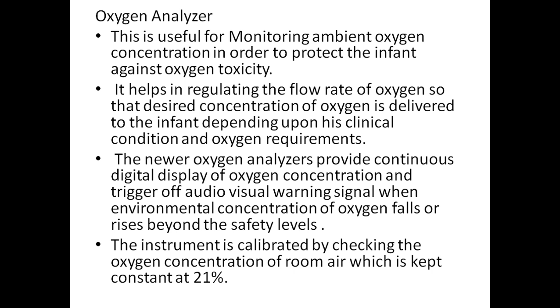The newer oxygen analyzers provide continuous digital display of oxygen concentration and trigger an audio-visual warning sign when the environmental concentration of oxygen falls or rises beyond the safety levels. The instrument is calibrated by checking the oxygen concentration of room air, which is constant at 21%. Oxygen is supplied through a central oxygen source or portable oxygen cylinders. Portable oxygen cylinders are expensive and not readily available in the district hospital or community health center.